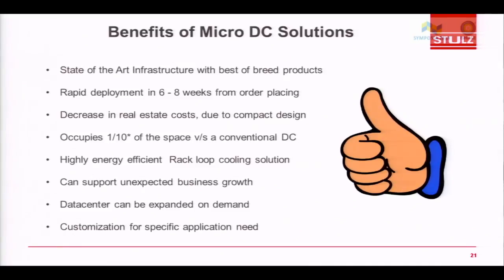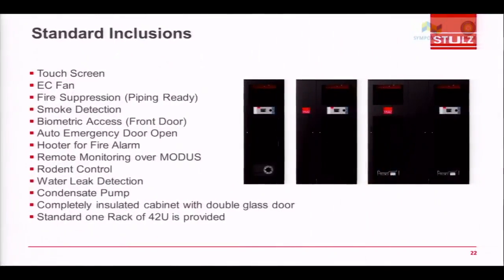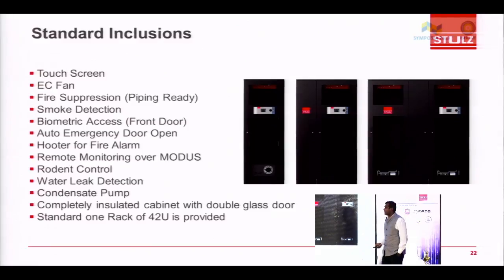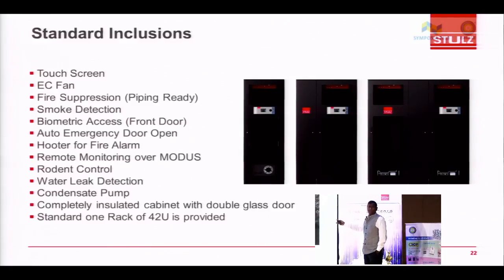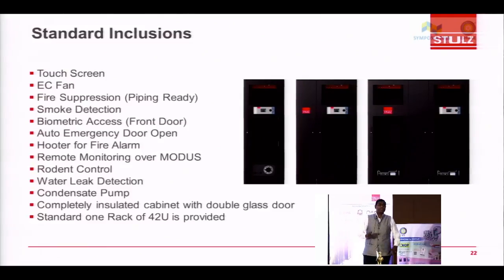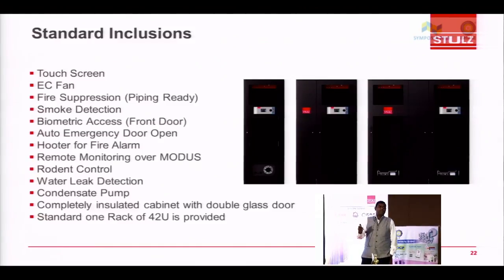It can support unexpected business growth, again because of the quick deployment possibilities. And it can be expanded on demand. Typical standard inclusions in the micro data centers would be the brain, the controller, the EC fan technology, the fire suppression, smoke detection, biometric access, alarms, detection systems, all of this. So all that you would expect in a traditional data center would be included. And then, if the demand increases, you could have one rack, multiple racks, or a high density rack, which you will see further as I move on with the slides. But you would have a lot of configurations where you move everything and ship it, and your edge computing need could be addressed and solved.